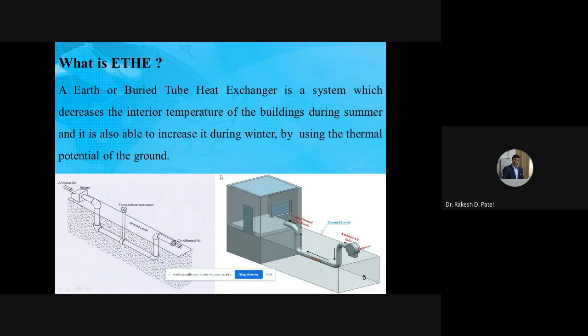So first of all, what is the earth tube heat exchanger? This heat exchanger plays a very important role in the energy transfer from the buried depth to the building or room. The earth or buried tube heat exchanger is a system which decreases the interior temperature of a building during the summer, and it is also able to increase it during the winter by using the thermal potential of the ground.